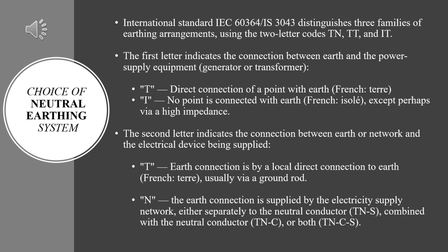The international standard IEC 60364 or Indian standard IS 3043 distinguishes three families of earthing arrangements using the two-letter codes TN, TT and IT. The first letter indicates the connection between earth and power supply equipment, that is generator or transformer. T denotes direct connection of a point with the earth, from the first letter of the French word 'terre'. I denotes no point is connected with the earth, from the first letter of the French word 'isolé', except perhaps via high impedance.